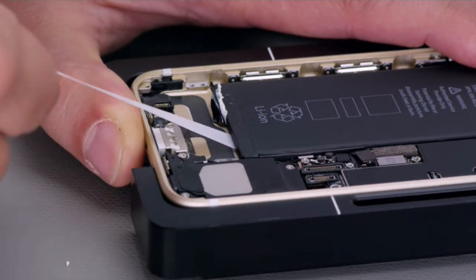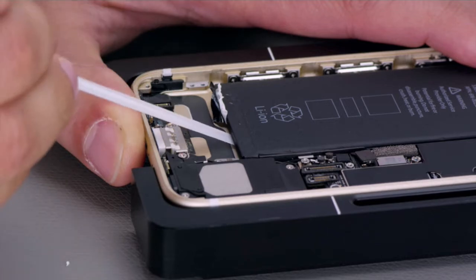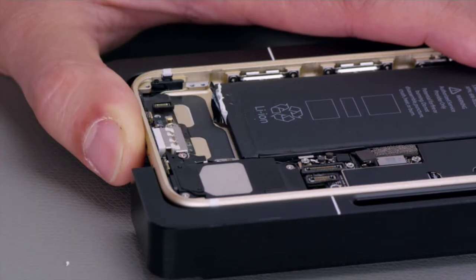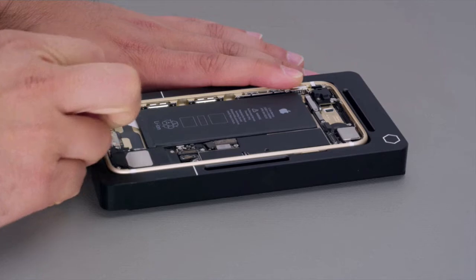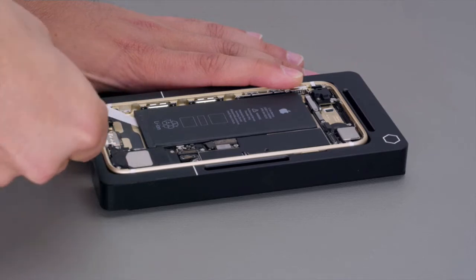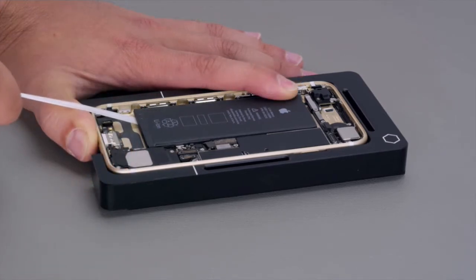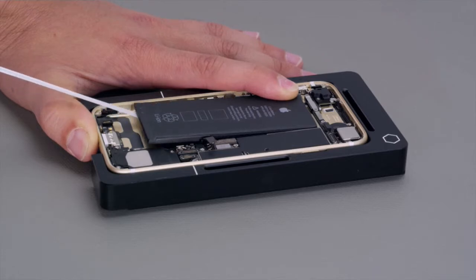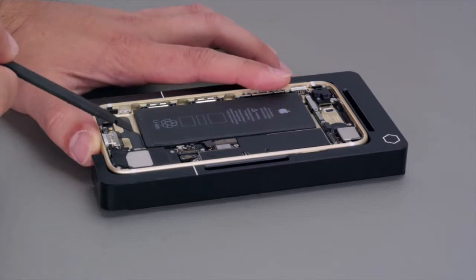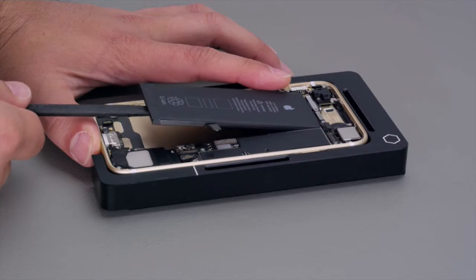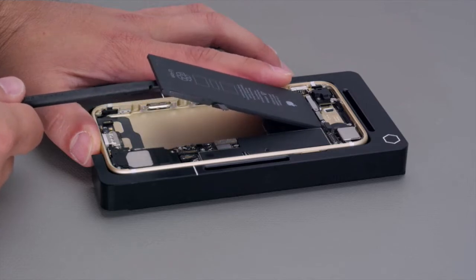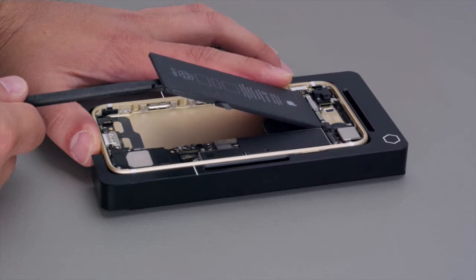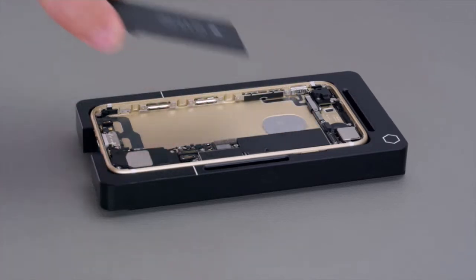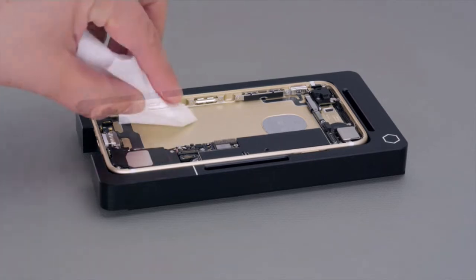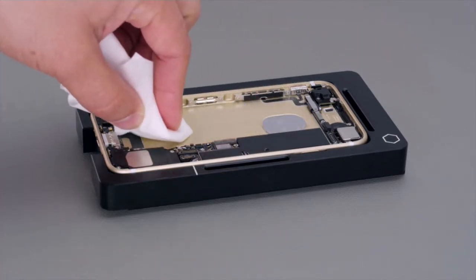Do not attempt to pry up the battery. Pull steadily until the adhesive strip releases. Grasp the adhesive strip on the other side. Slowly pull toward the bottom of the enclosure until it releases. Use a black stick to gently lift the bottom of the battery. Do not force the battery out. If the battery gives any resistance, stop the repair and replace the whole unit. Remove the battery. Use IPA wipes to clean the enclosure.